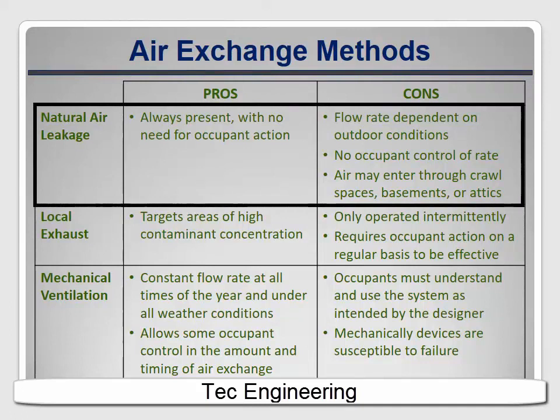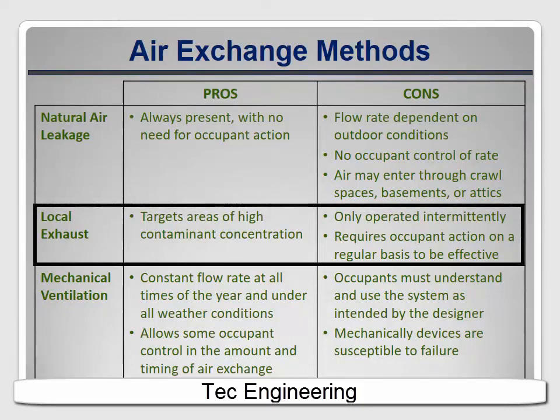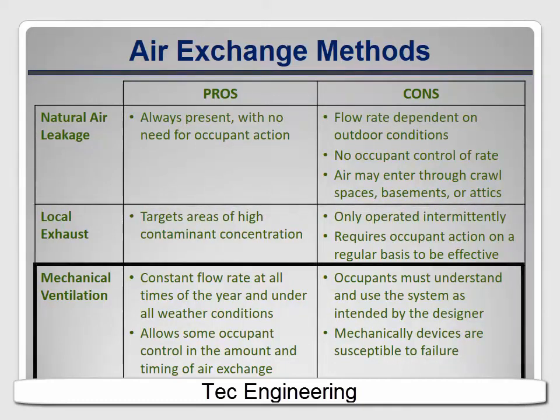Each of these types of ventilation has advantages and disadvantages. Natural leakage is always present and doesn't require any occupant action to make it occur. But it varies with weather conditions, so there are times of the year when it provides little air exchange. The occupants have no ability to control the rate or timing to suit their needs, and they can't control where the air comes from — it might be coming up through a damp crawl space. Local exhaust does very well at targeting big sources of contaminants, but it only runs when the occupants turn it on. If they don't use it regularly, it's not very effective. Mechanical whole building ventilation provides constant, year-round exchange and gives the occupant some control over the flow rate — but only if the occupants understand and use the system properly. In addition, mechanical devices are prone to failure and don't always get repaired promptly or correctly.